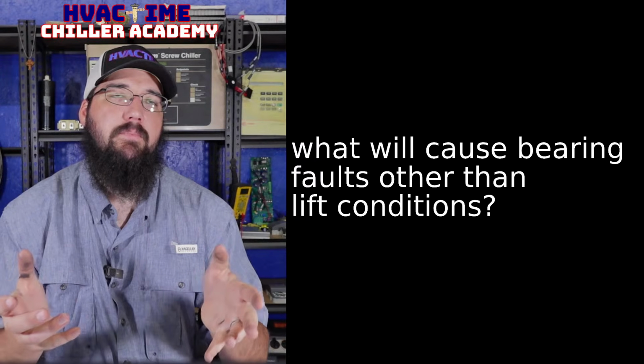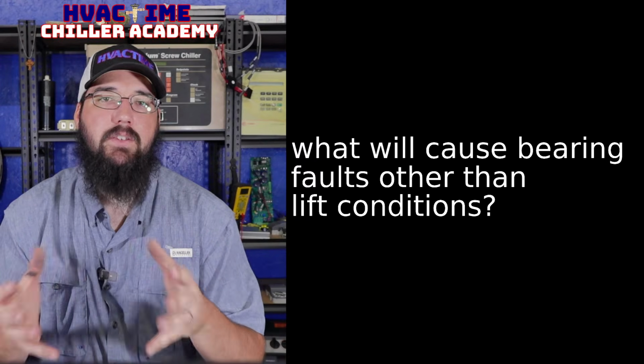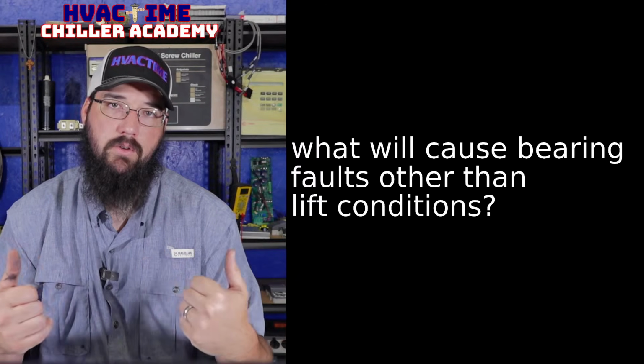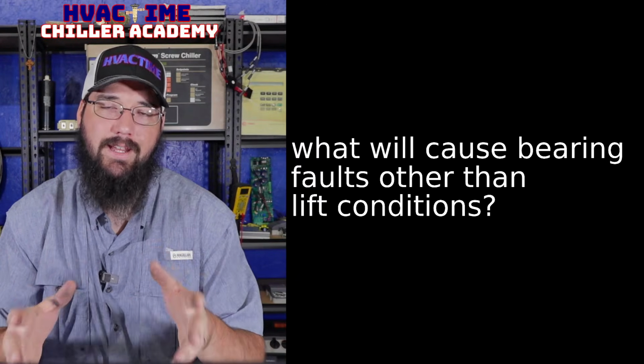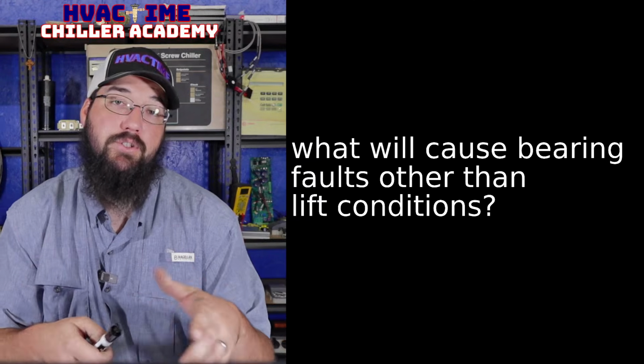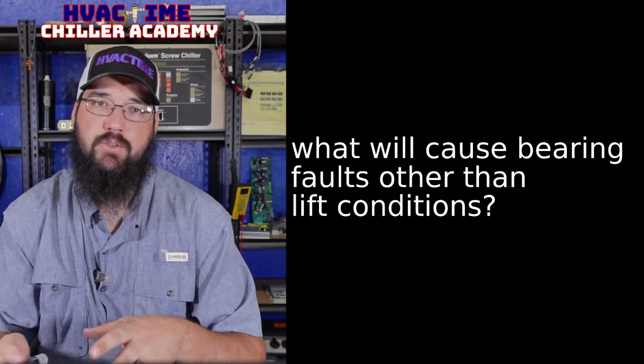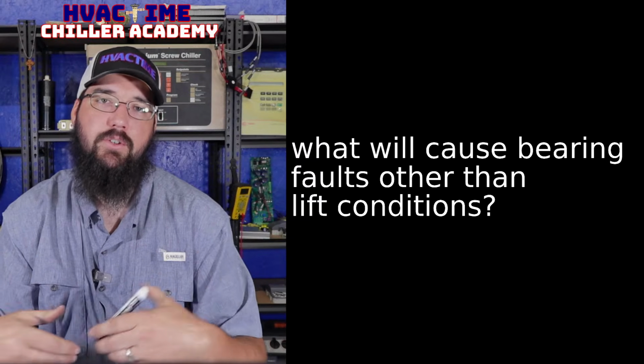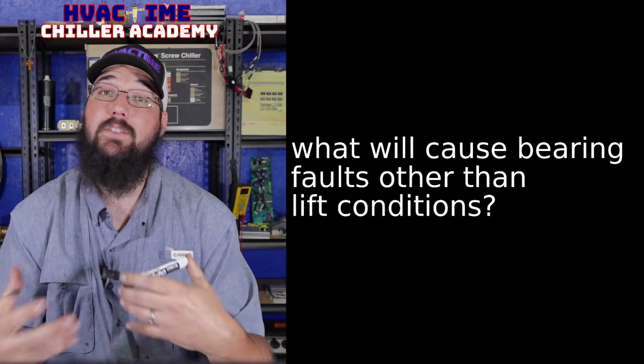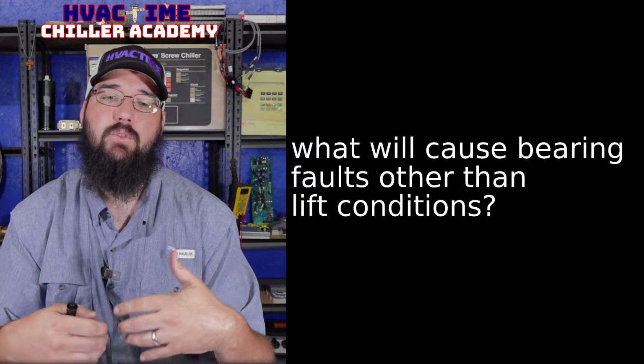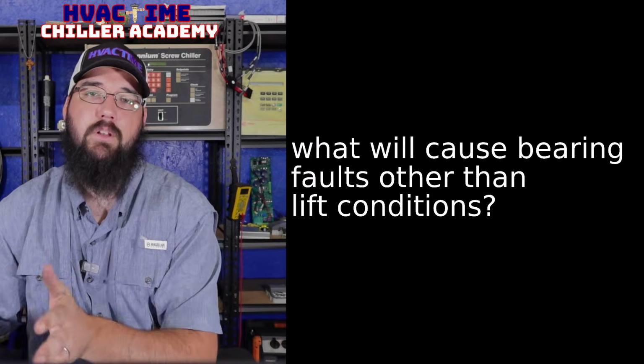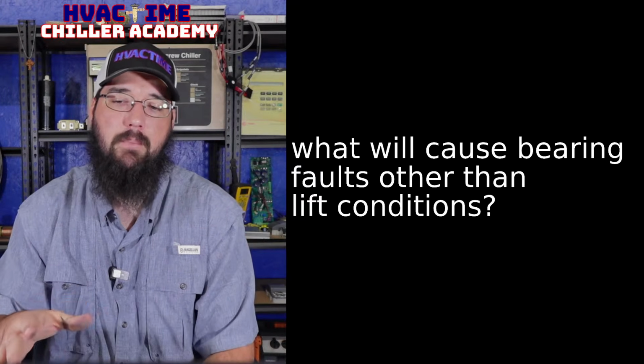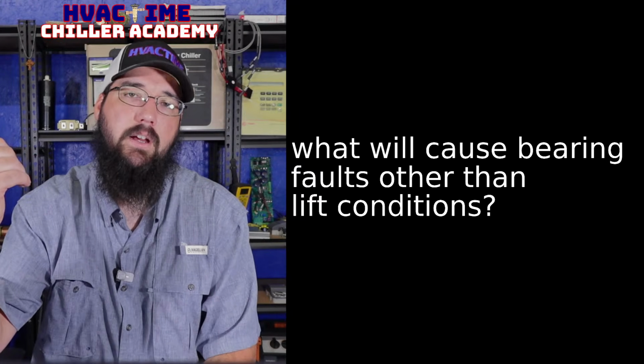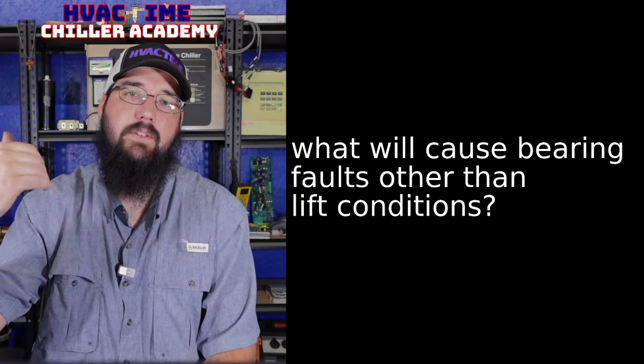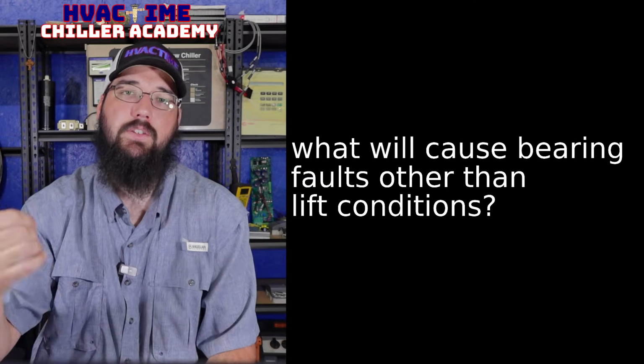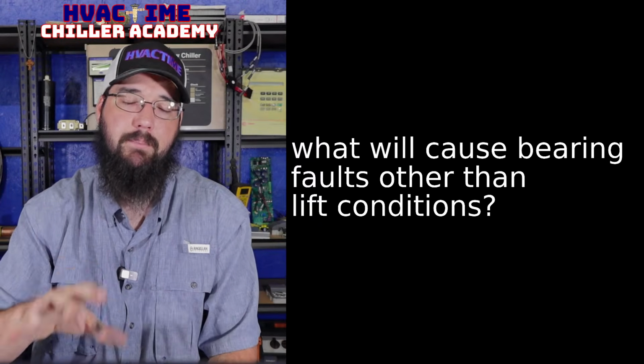So, yes, high lift, or even low lift for that matter, but more specifically high lift, that's going to push you into surging potential. And as we push close into surge, that's when we're going to start having instability in the impeller due to that high lift and it trying to not go into a surge, right? So just doing a quick recap on what we're saying when we say high lift or just lift issues causing surging or causing bearing faults.